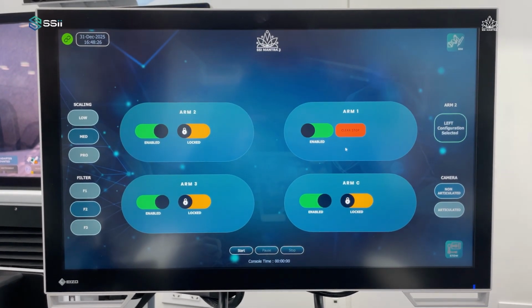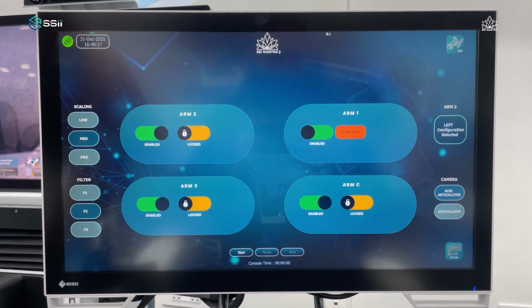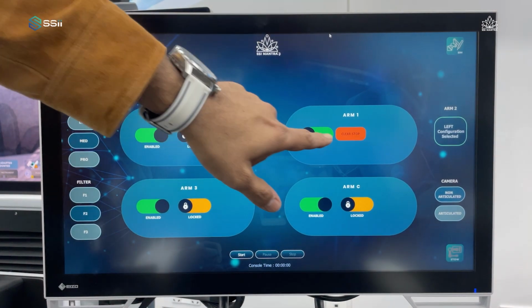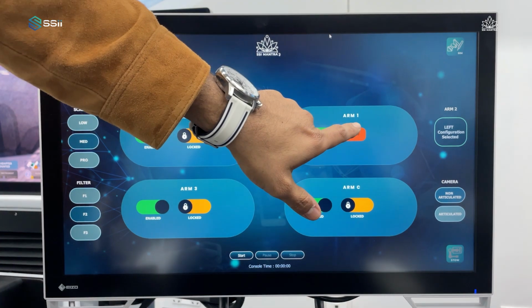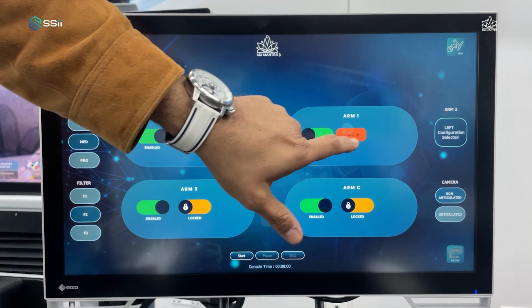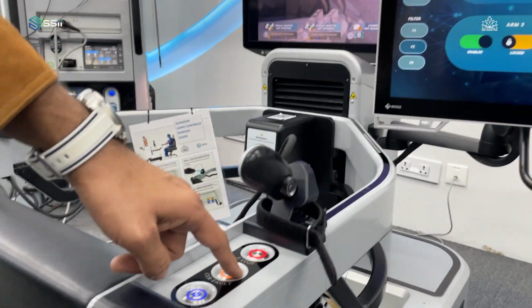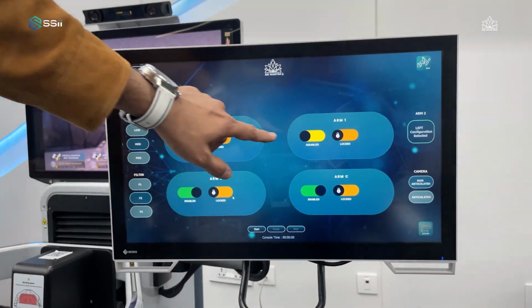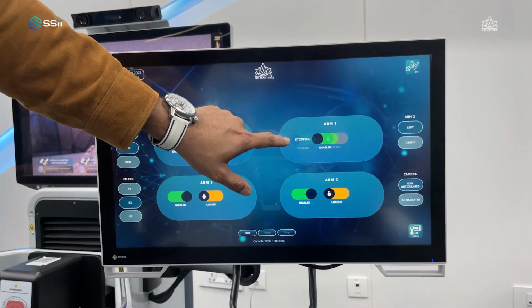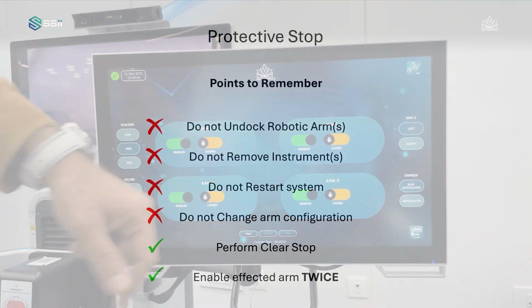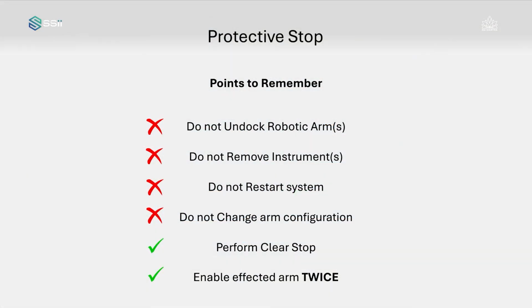A visual message is displayed on the SCC 2D screen, where the affected arm control displays a clear stop button highlighted in red. Recovery procedure: press the clear stop button on the SCC 2D control screen, or press the clear fault button on the SCC control panel. After clearing the stop, the arm must be enabled twice before resuming operation. Here are some important points to remember while the system is in protective stop. No need to undock the arm or remove the instruments. No need to restart or reset the system. No need to change arm configuration.